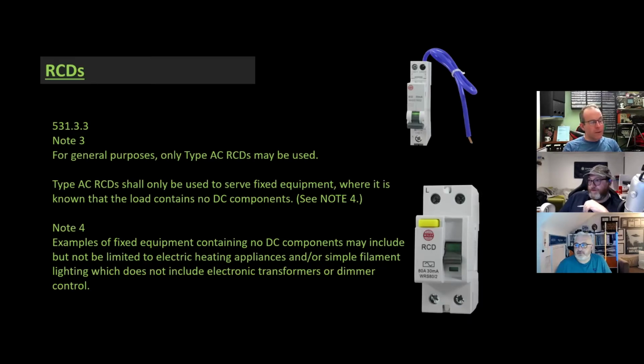Basically what it used to say was, for general purposes, type AC RCDs may be used, which is what it says now, and they've altered it by removing a single letter, which has a huge impact - it now says, for general purposes only, type A RCDs may be used. So basically, type AC is going away. I apologise, chaps, I've realised I've made a mistake on that - yeah, there you go. It's crazy, it's just AC, one little line through the letter C - that's all they're going to do, but that's a huge change. This is what happens when you put a PowerPoint together the afternoon it's coming out, you make mistakes. So yeah, that should say type A - there's a surprise, guys.